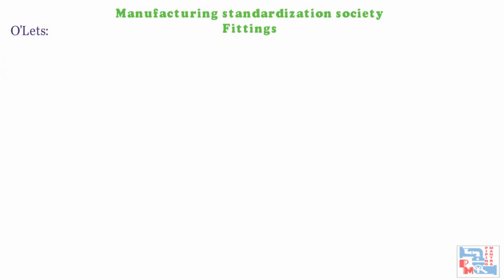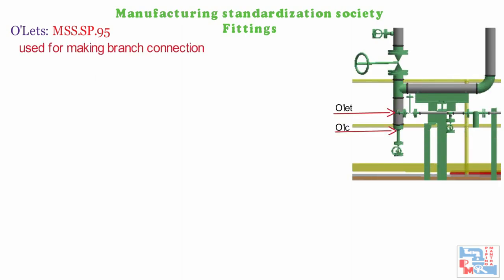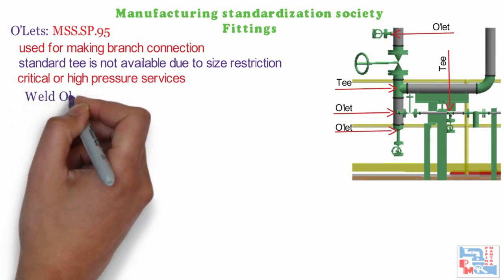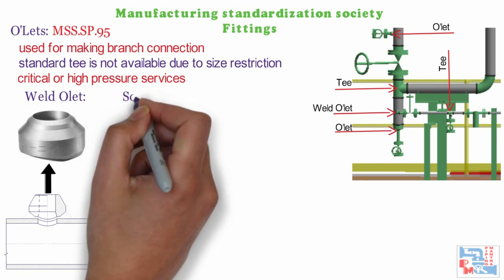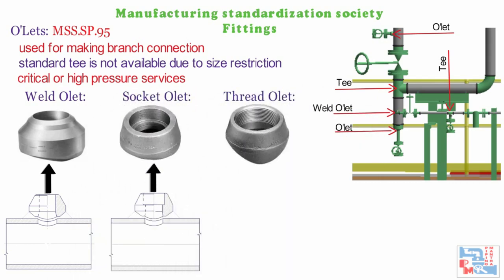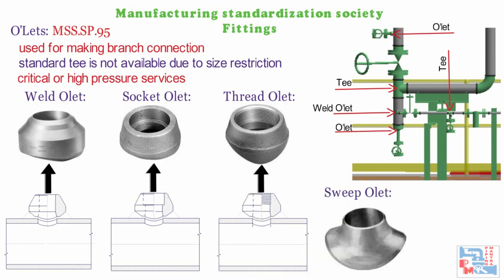Next are olet fittings per MSS SP95. Olets are used for making branch connections where standard Ts are not available due to size restriction, or where critical or high-pressure services prevent direct stub-out welding. Types include: weldolet, for butt welded branch connections; sockolet, for socket welded branch connections; threadolet, for threaded branch connections; and sweepolet, which is similar to a weldolet but has an integrally reinforced pad for butt welded branch connections — though it is weaker than a weldolet strength-wise.